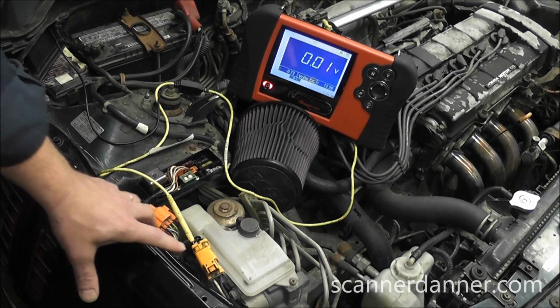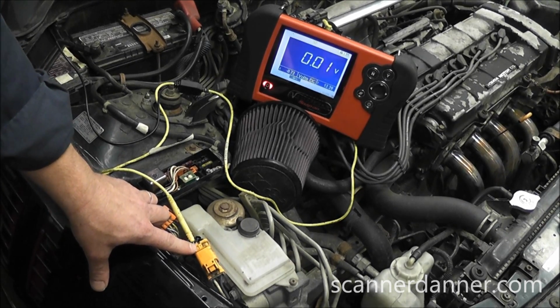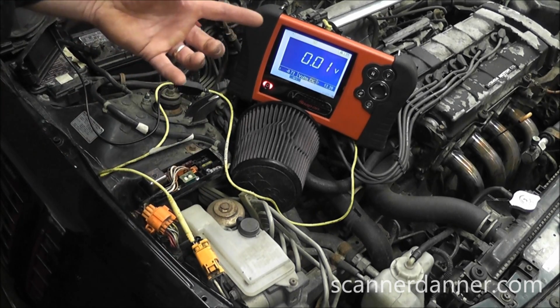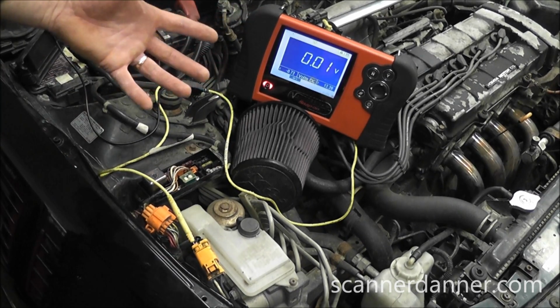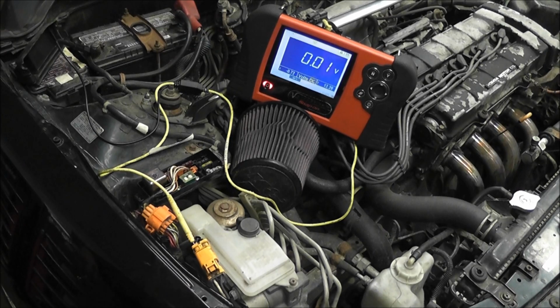So we are having contact issues with the brushes on this motor. There is a bias line voltage used for diagnostic purposes. I'm going to come back to the wiring diagram one more time to explain that further.